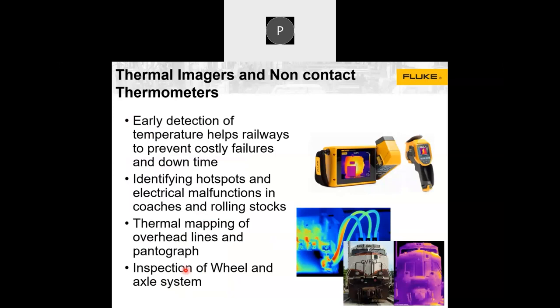And then thermal images - some applications I have given here. With thermal images you can detect thermal conditions, because many times when you have more wires and cables in your panels, you may not know what is the condition - which wire is carrying current and which is not. By looking with your naked eyes you will not be able to find out. But if there is a fault, or even if current is passing through a cable, that cable will be more heated or have a higher temperature than the non-conducting one. That's why it's very easy to identify the condition of cables and subsystems - even a switch, cable, or relay - whether it is functioning or not.